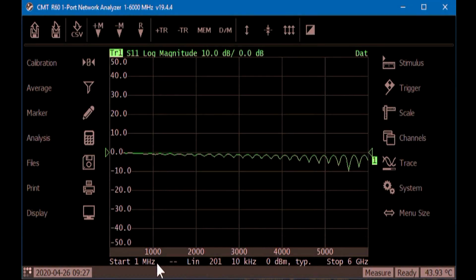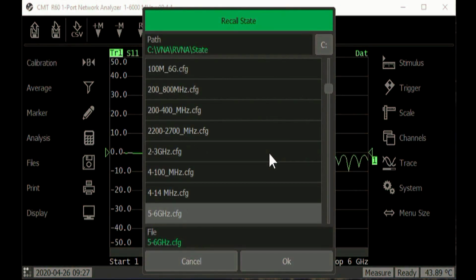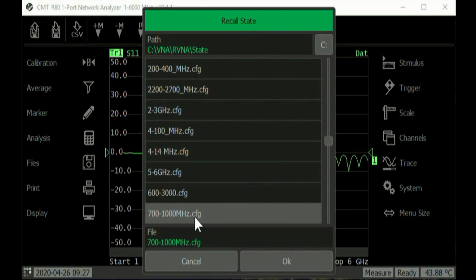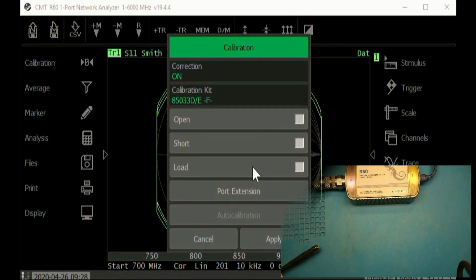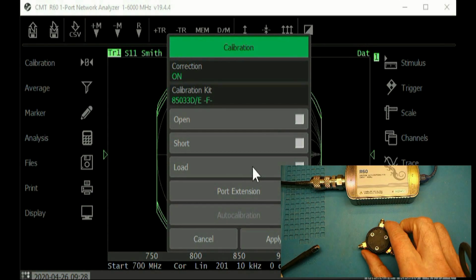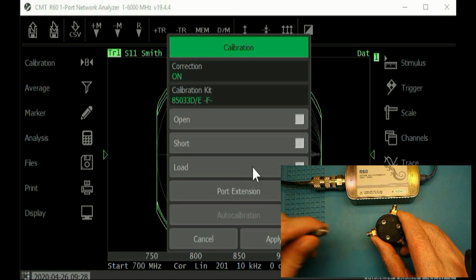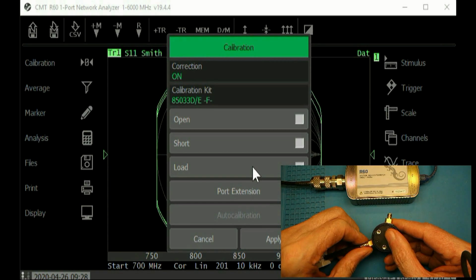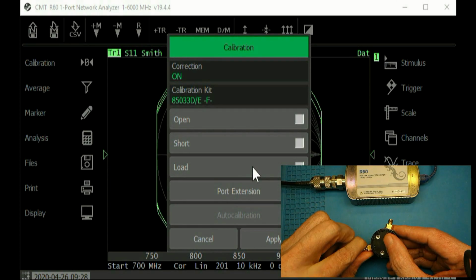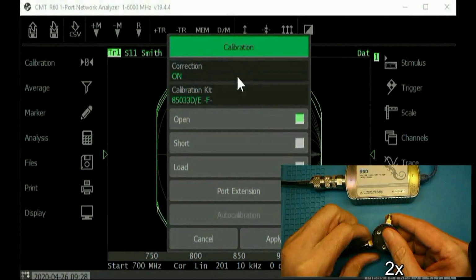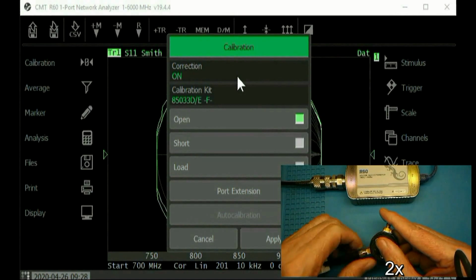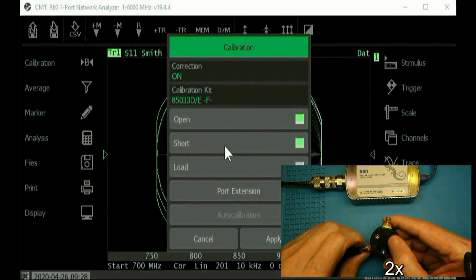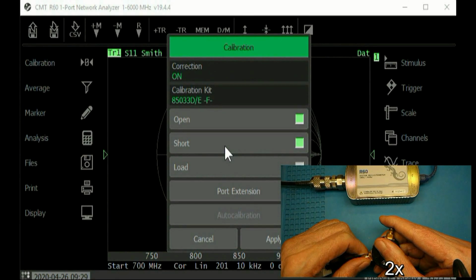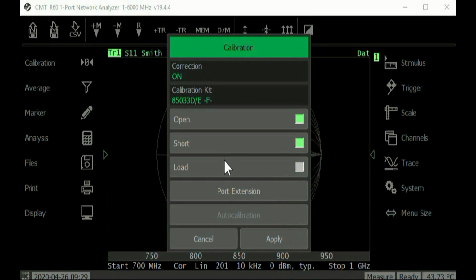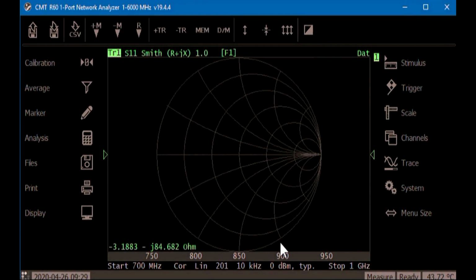Frequency range must be set to something fitting the actual measurement. Here is a previously saved frequency range that covers the 868 MHz antenna. Next step is S11 calibration: open, short and load. Confirm for each setting. Press apply to save these settings, and now this window can be minimized.